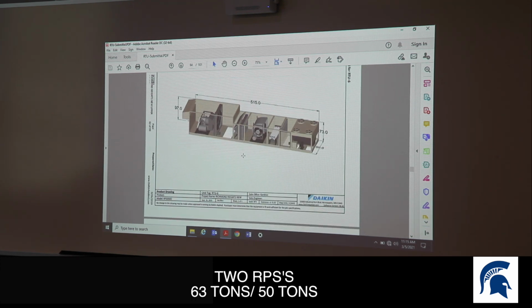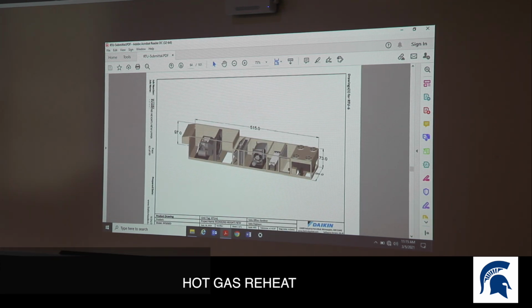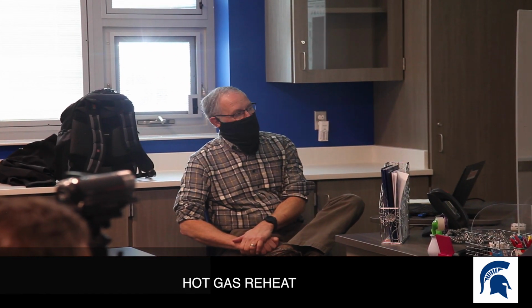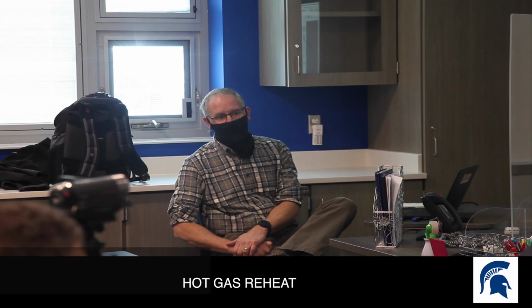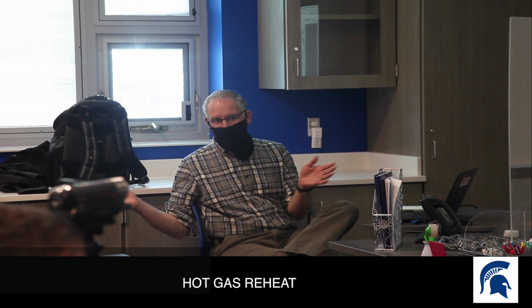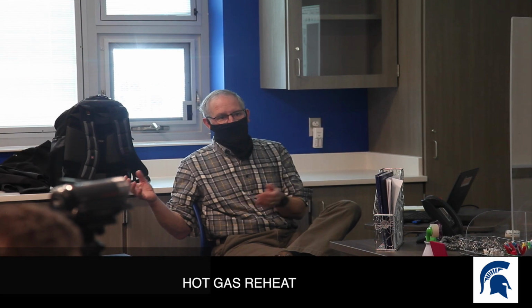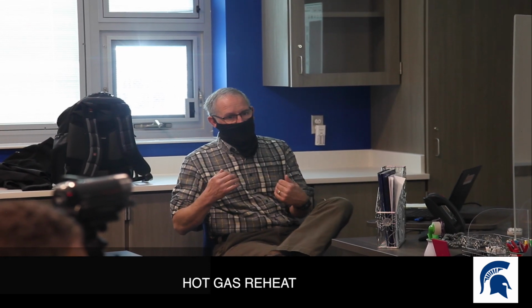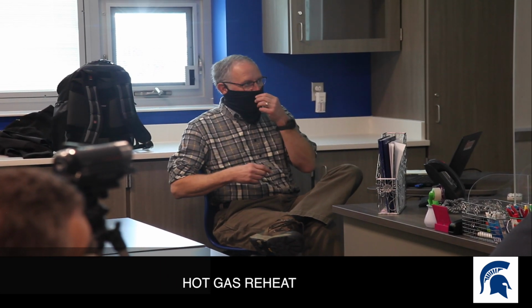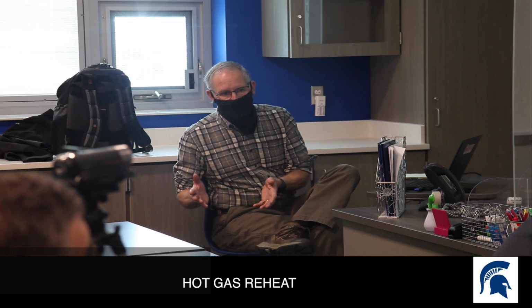Now, let's take a minute and talk about hot gas reheat and why it's there, okay? These machines sense, I believe it's return air humidity in your space, okay? One of the situations that has been prevalent in schools for years is you don't load a classroom like it's designed, and the cooling doesn't have to run very much for it to get to set point, and it gets humid in there. It gets like damp. These machines will dehumidify based on the return air humidity. So you could see heating and cooling running at the same time.